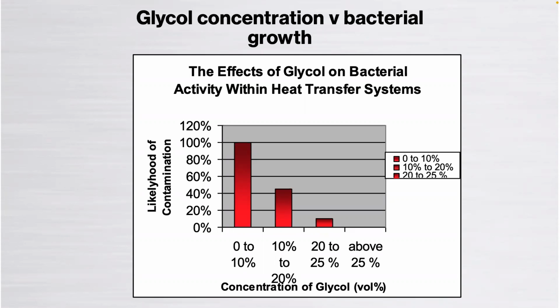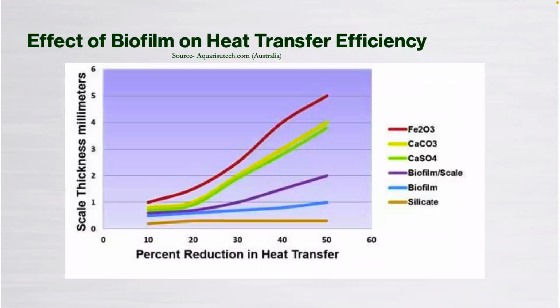So maintaining above 25% glycol is really important. And as we look to be more energy efficient and we want to clean up our systems, or we want to maintain new systems in a good condition, having a good level of water quality is important. But if we do get biofilm, it's actually more of a thermal insulator, as it were, than scale. So the last thing we want is scale, but even if we're not in a hard water area, the last thing we want is biofilm at the same time, for the reasons I alluded to before in terms of erosion, corrosion for a start, and it's affecting inhibitor regimes, but also for energy performance.